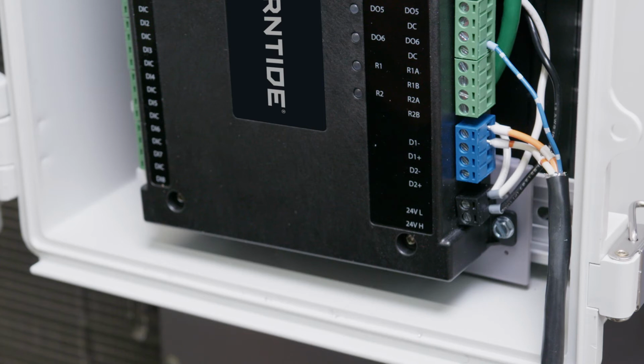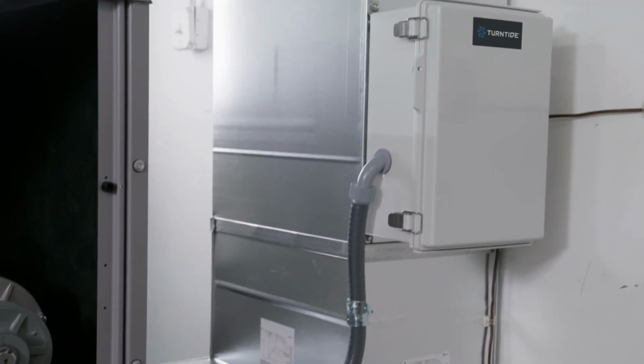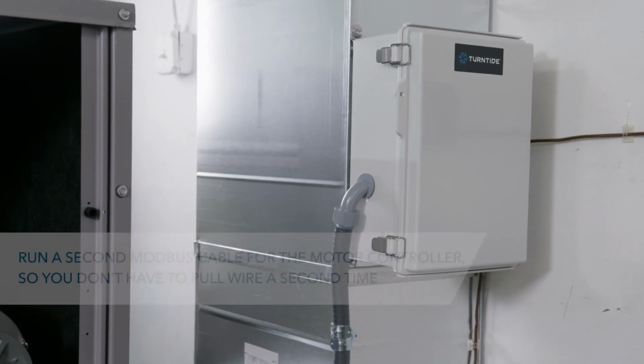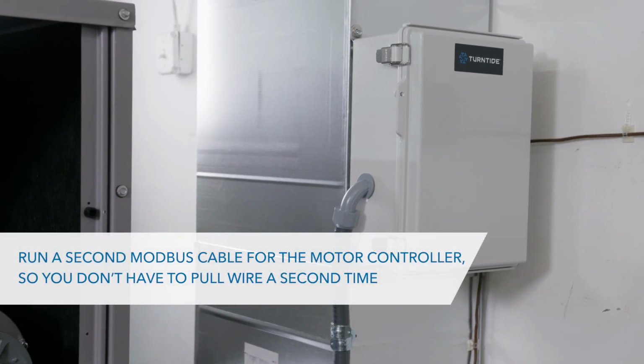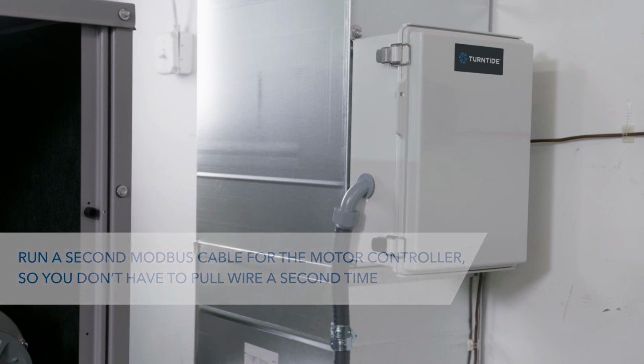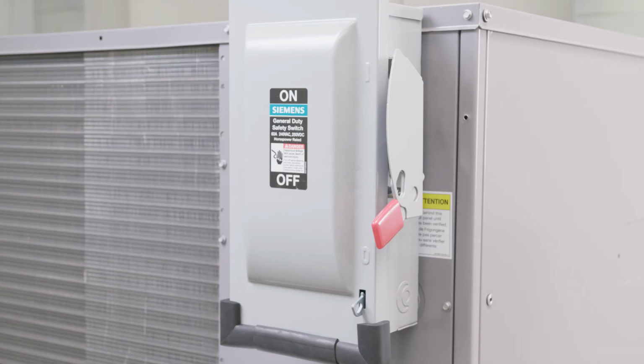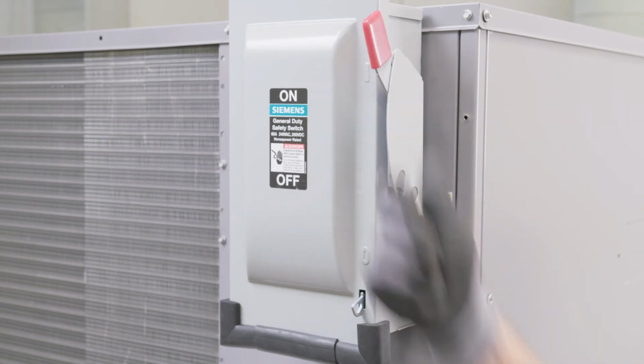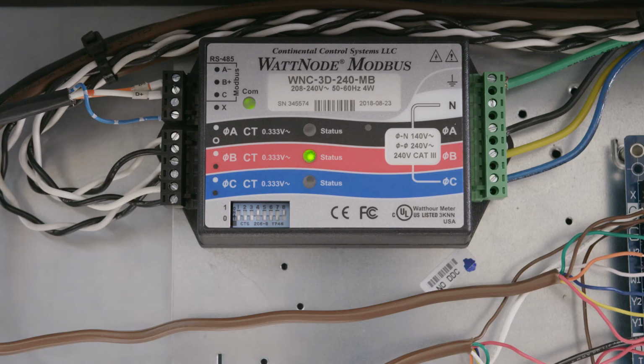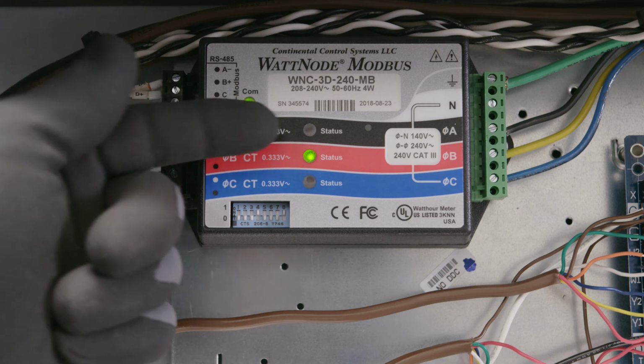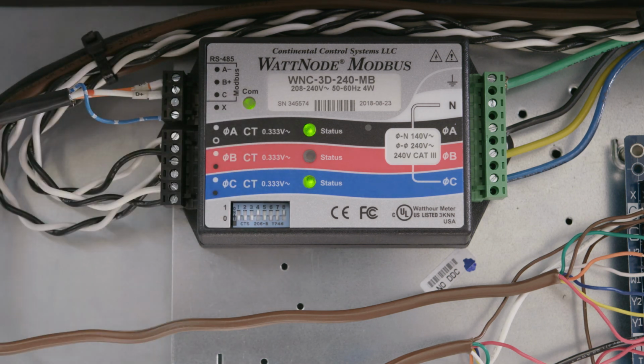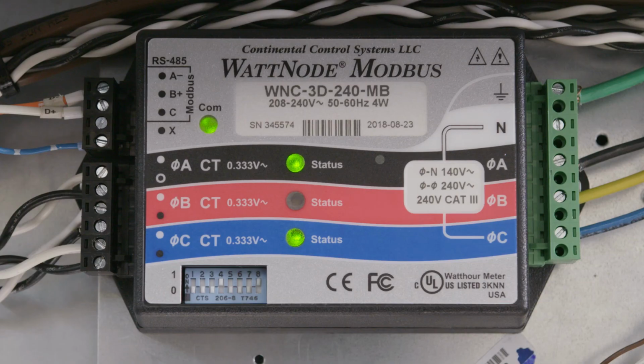If you have to mount the supervisor remotely and have to use a flex conduit, you might want to run a second modbus cable for the motor controller, so you don't have to pull wire a second time. Once you have completed these steps, apply power to the HVAC unit. The LED for the communication should be pulsating green, indicating it's communicating to the supervisor. When the fan motor is running, the 3 LEDs on the meter should be pulsating green. This is a normal condition when the fan is running and the CTs are reading the power use of the motor.